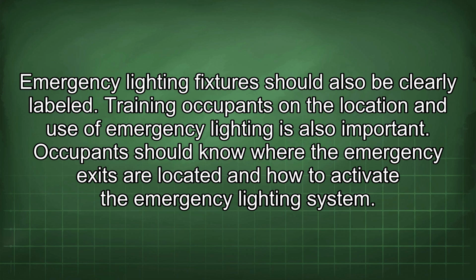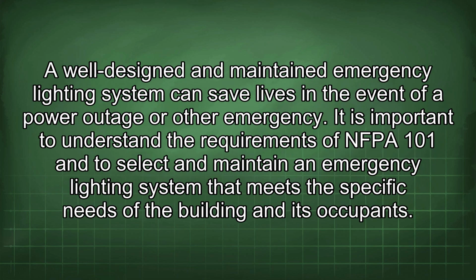Training occupants on the location and use of emergency lighting is also important. Occupants should know where the emergency exits are located and how to activate the emergency lighting system. A well-designed and maintained emergency lighting system can save lives in the event of a power outage or other emergency. It is important to understand the requirements of NFPA 101 and to select and maintain an emergency lighting system that meets the specific needs of the building and its occupants.